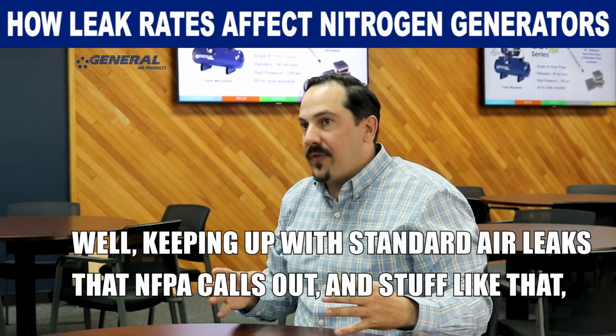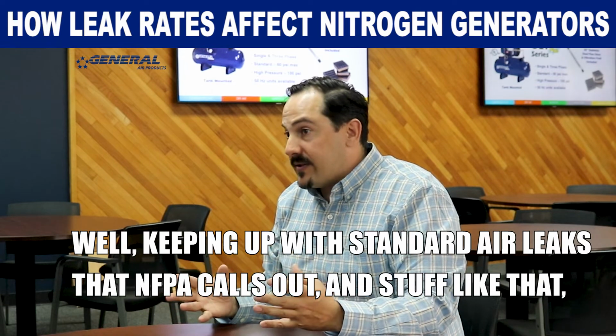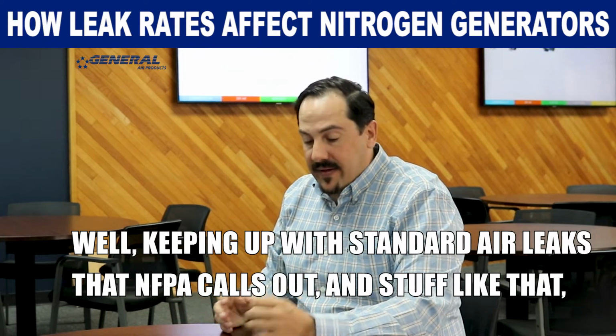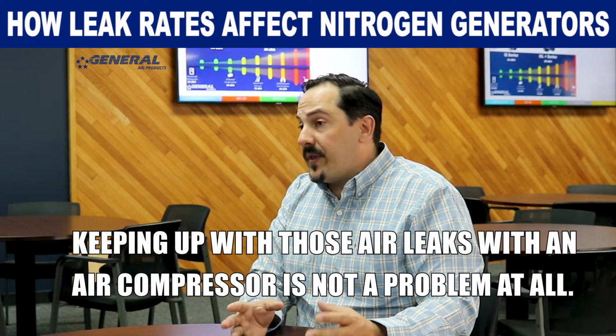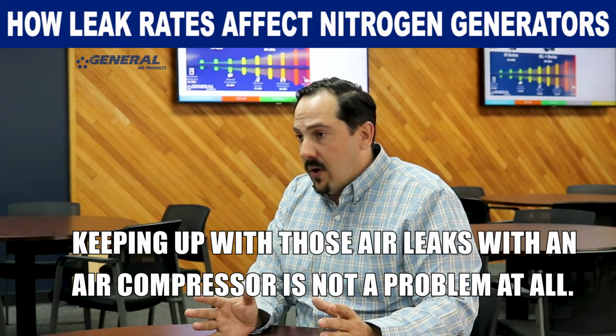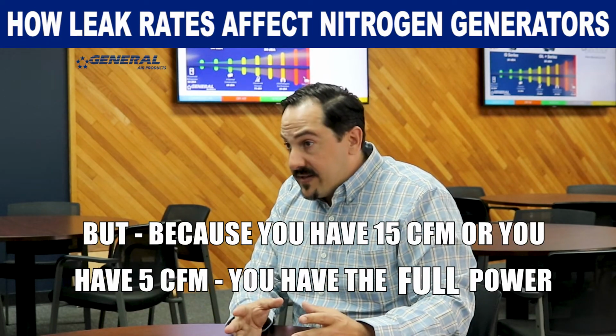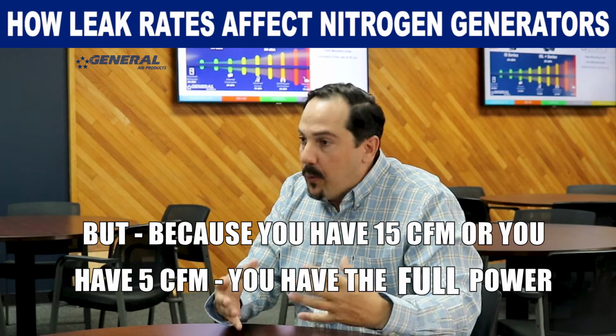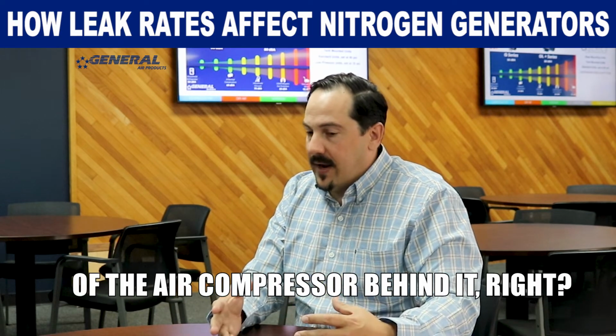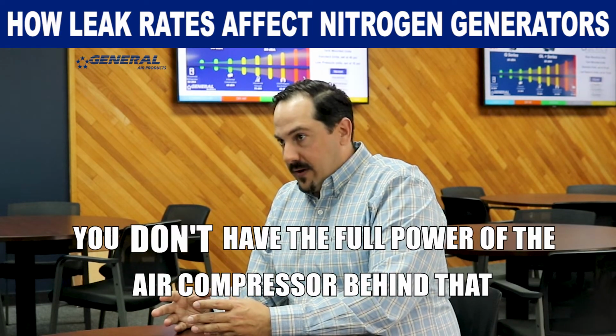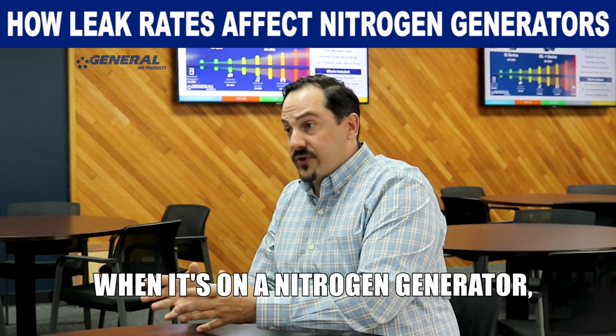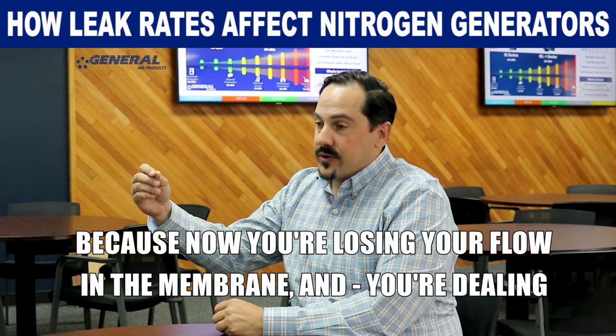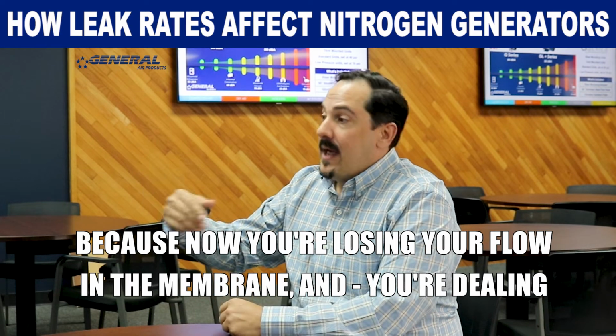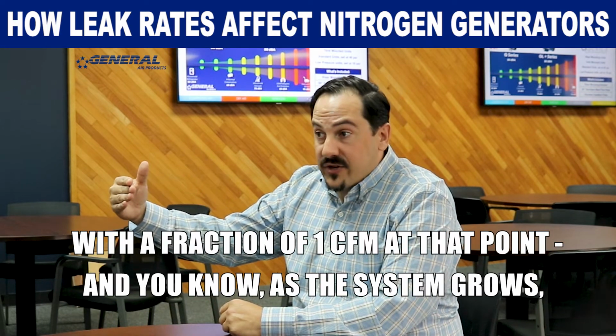Keeping up with the standard air leaks that NFPA calls out with an air compressor is not a problem at all, because you have 15 CFM or 5 CFM, the full power of the air compressor behind it.